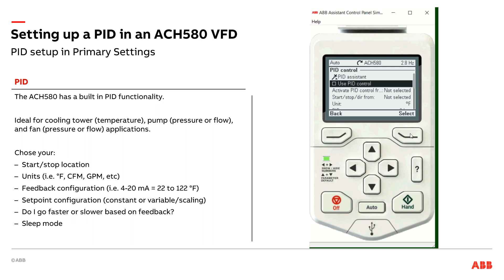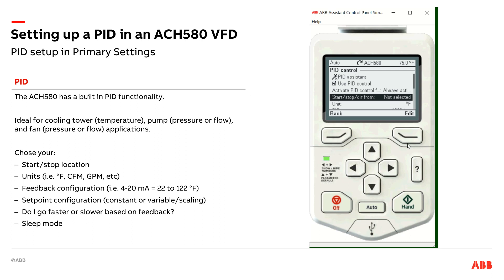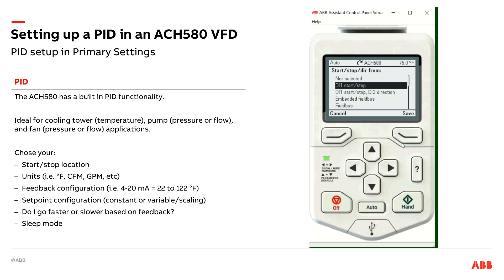First thing I'm going to do is say yes, I want to use PID control. It is always active. So my first main decision here is where's my start/stop and, if applicable, my direction command — say if I have de-ice mode for a cooling tower in a northern climate. I'm going to say my start/stop is on digital input 1. I don't need to reverse, but if I wanted reversing on digital input 2, I could have selected that second option. So digital input 1 is my start/stop.